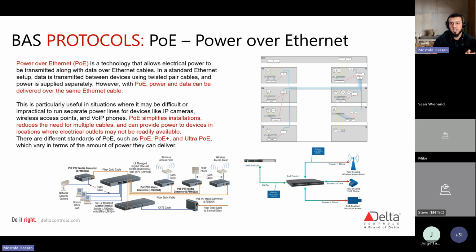So the way it works is simple. Ethernet cable that meets the Cat-X standard consists of 4 twisted pairs of cable. Now, PoE sends power over these pairs to the PoE-enabled devices. The first PoE standards use the first 2 twisted pairs to transmit data and the other 2 to transmit power. Now, with the newer PoE standards, power and data are both sent over all 4 twisted pairs.